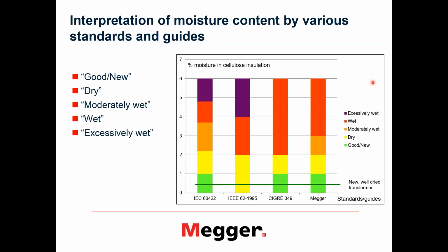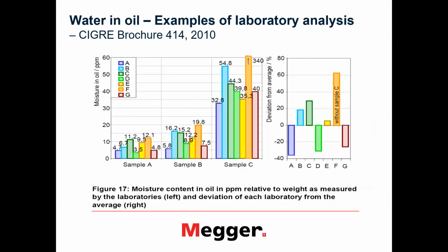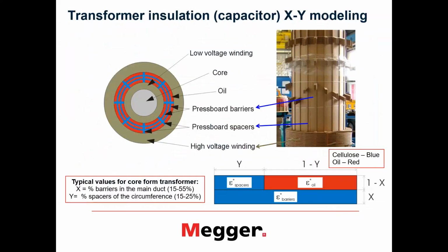No historical data are involved here. The whole temperature correction is based on the activation energy of the paper and oil, and they are combined in this model. You combine the paper, which is blue, you combine the oil, and depending on this ratio and the activation energies, you calculate the correction factors for shifting curves or calculating results at 50 Hertz or 60 Hertz. Another thing regarding this question is whether it's historical trend data or a direct result coming directly with the test itself. Well, it is taken from direct measurement, which you do today.